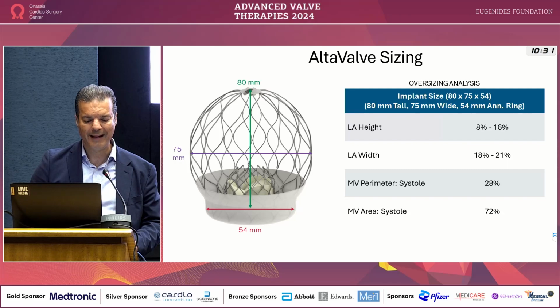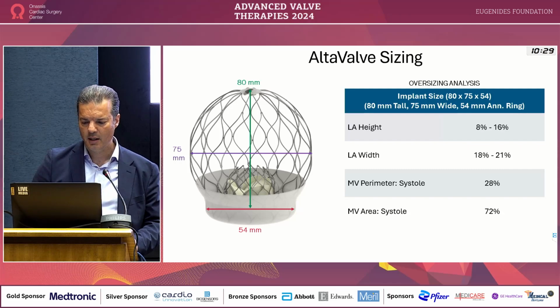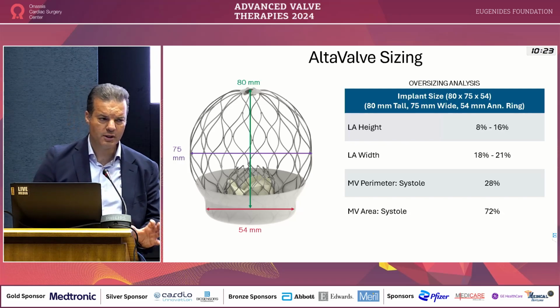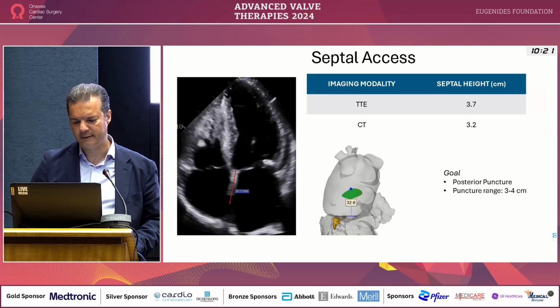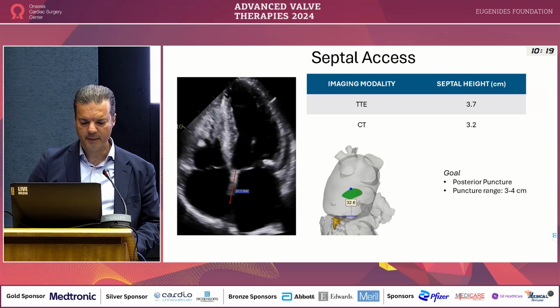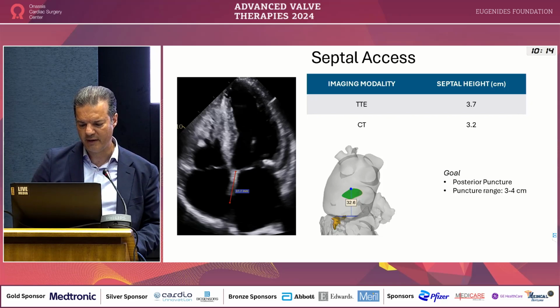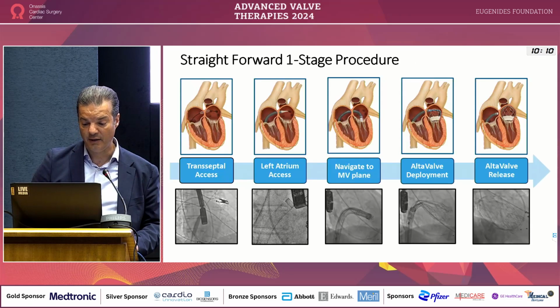So looking at all that, we decided on an implant of a 54 on the annular ring and 75 by 80 on the cage. That will give us a height oversize around 15% max and width oversize about 20%, which is just about what we need for an implant. Transseptal puncture needs to be above 3 centimeters. We have a projected 3.5 to 4 centimeters. We go posterior and inferior.